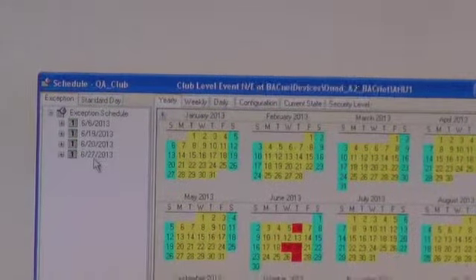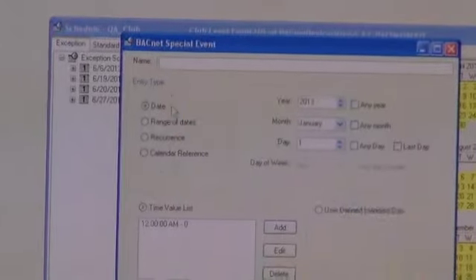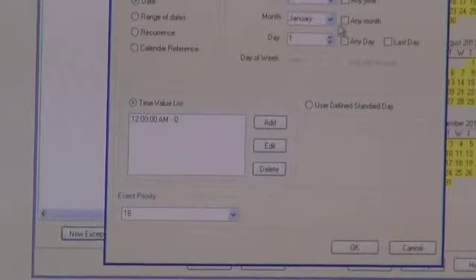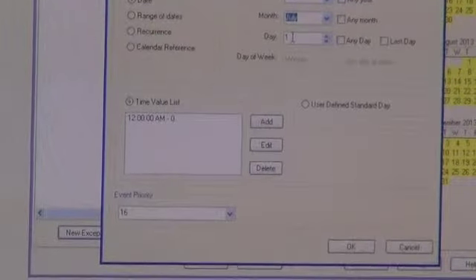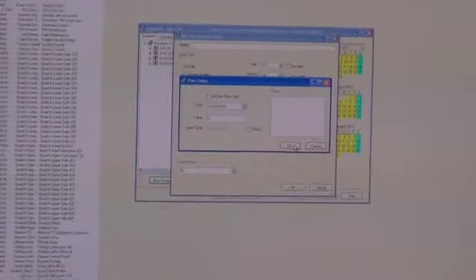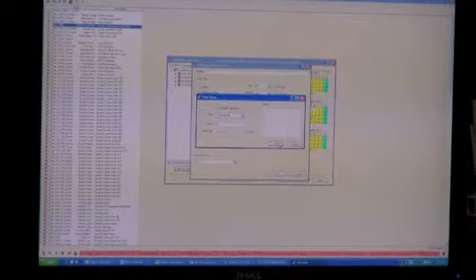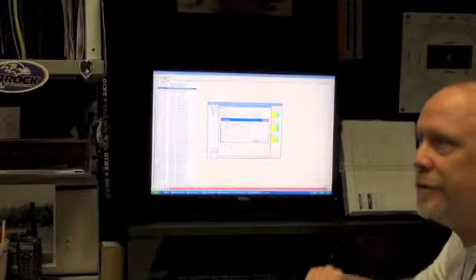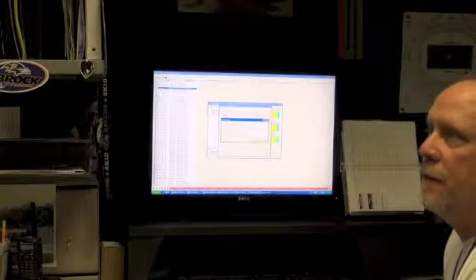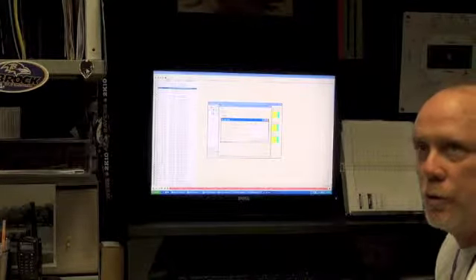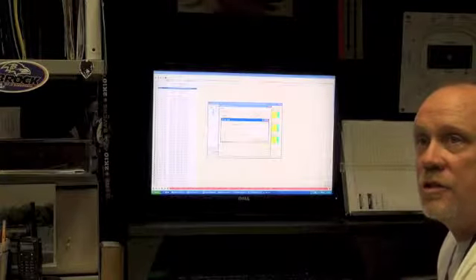What we would do is schedule the event. We name it, date it, whatever day it would be, say July 1st, and you'd put the time in there for when you wanted it to go on. We would normally start smaller units an hour before the event, to give them a chance to catch up by the time it gets occupied with people, so that it's cool or heated, whichever it may be. The smaller locker rooms, suites, the large areas, the club level areas, we start 2 to 3 hours earlier. It's such a large area.